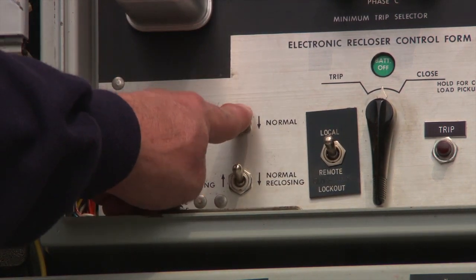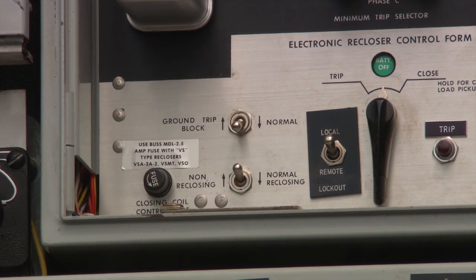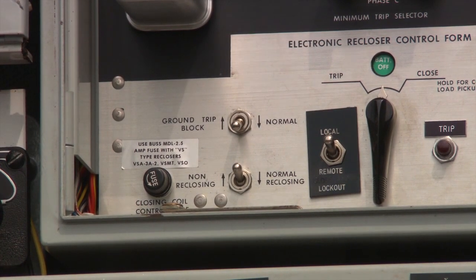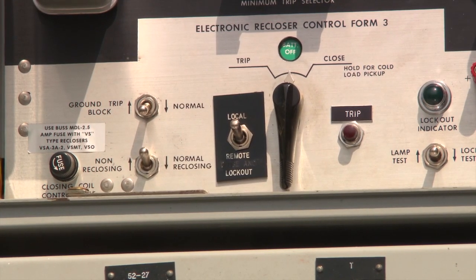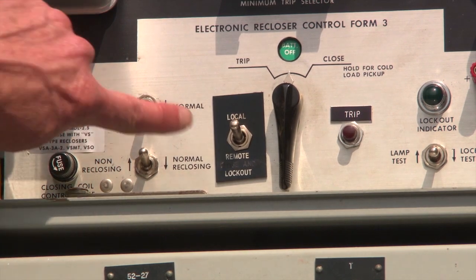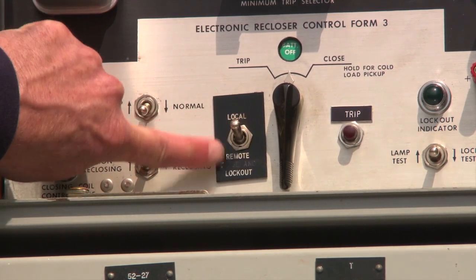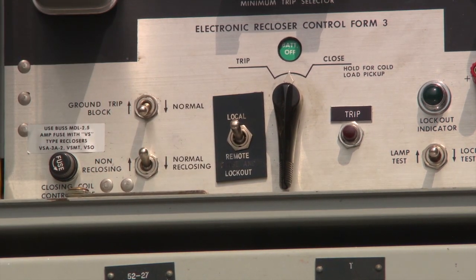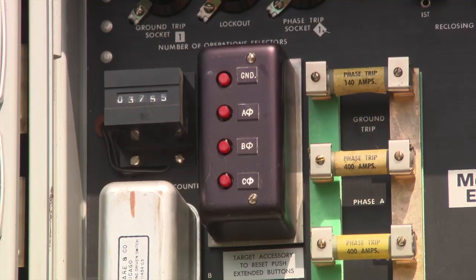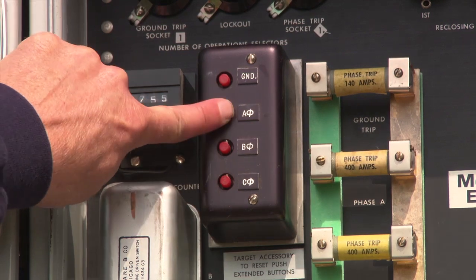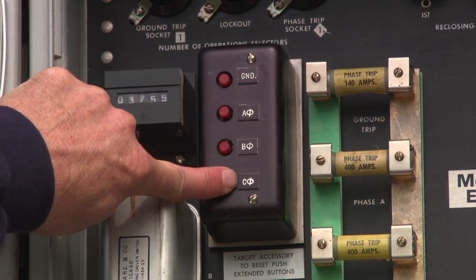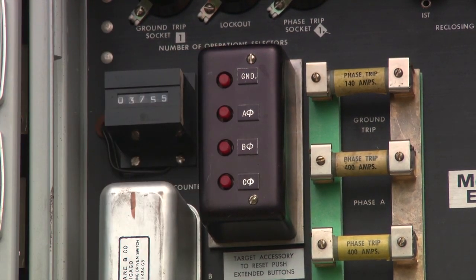The ground trip blocking switch should be in the normal position. And the local remote switch should be in the local position. Reset the A, B, and C ground fault target indicator. This device records whether a phase or a ground fault caused the recloser to operate.